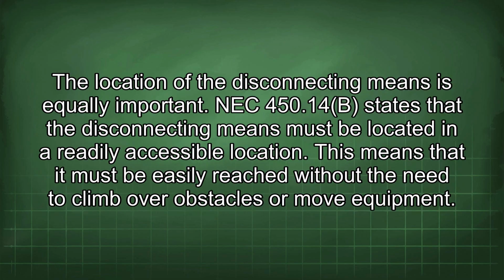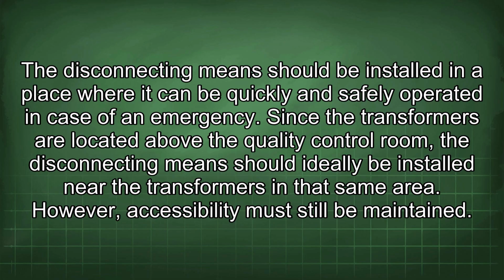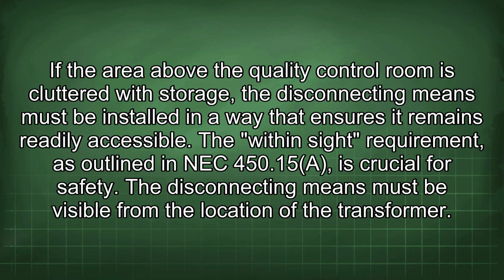The location of the disconnecting means is equally important. NEC 450.14(b) states that the disconnecting means must be located in a readily accessible location. This means that it must be easily reached without the need to climb over obstacles or move equipment. The disconnecting means should be installed in a place where it can be quickly and safely operated in case of an emergency. Since the transformers are located above the quality control room, the disconnecting means should ideally be installed near the transformers in that same area. However, accessibility must still be maintained. If the area above the quality control room is cluttered with storage, the disconnecting means must be installed in a way that ensures it remains readily accessible.